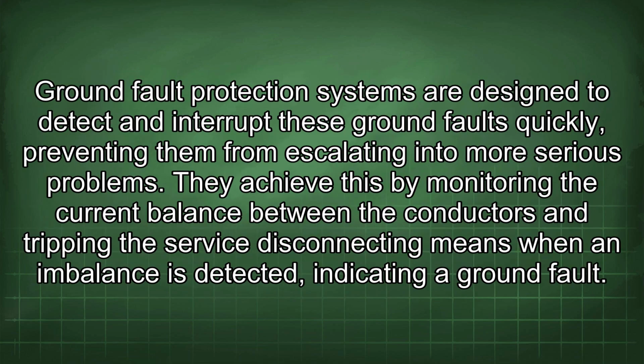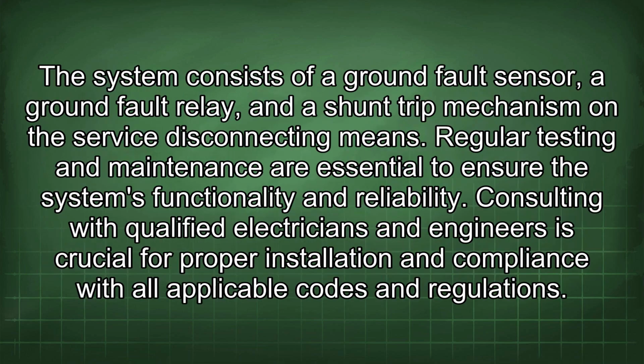Ground fault protection systems are designed to detect and interrupt these ground faults quickly, preventing them from escalating into more serious problems. They achieve this by monitoring the current balance between the conductors and tripping the service disconnecting means when an imbalance is detected, indicating a ground fault. The system consists of a ground fault sensor, a ground fault relay, and a shunt trip mechanism on the service disconnecting means. Regular testing and maintenance are essential to ensure the system's functionality and reliability.